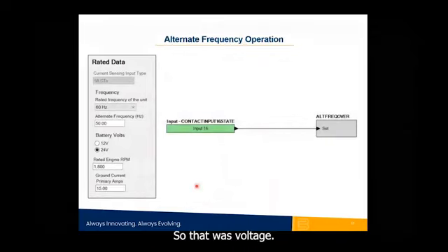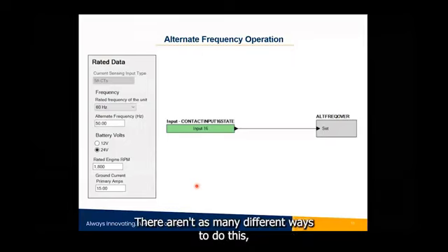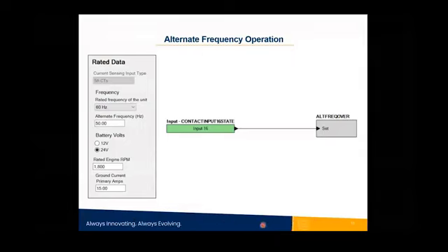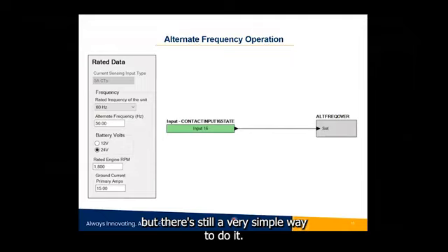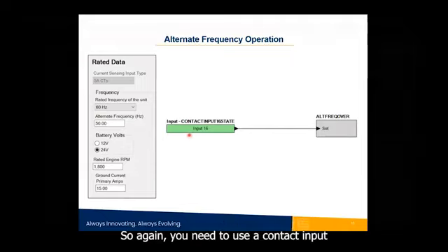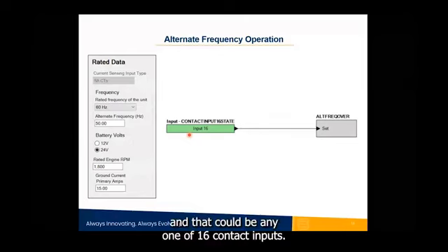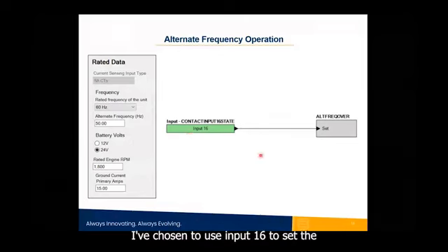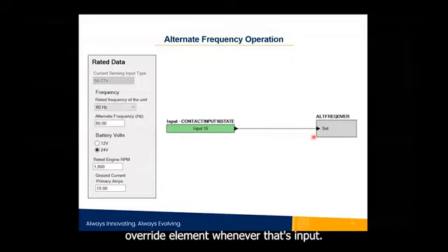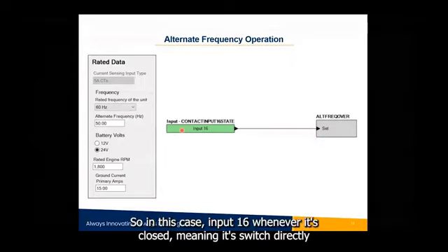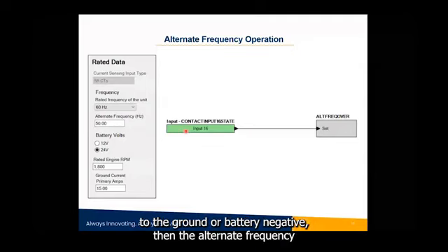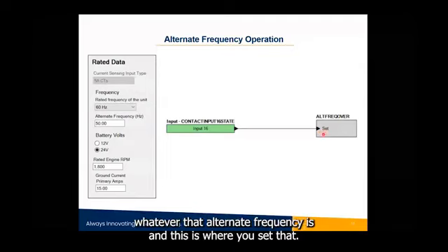So that was voltage. Now let's talk about frequency. For alternate frequency detection, there aren't as many different ways to do this, but there's still a very simple way to do it. Again, you need to use a contact input, and that could be any one of 16 contact inputs. I've chosen to use input 16 to set the override element. Whenever that input is closed, meaning it's switched directly to ground or battery negative, then the alternate frequency override logic element is set, and the controller now adopts whatever that alternate frequency is. And this is where you set that.